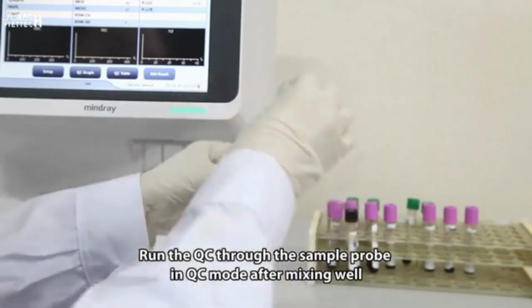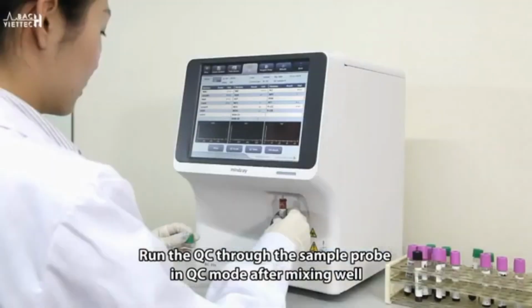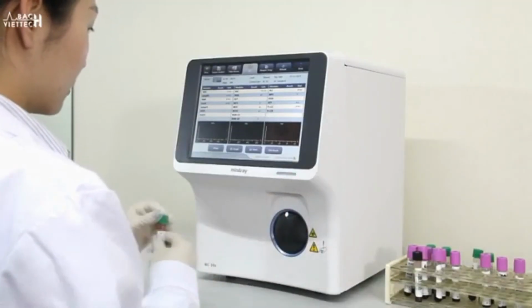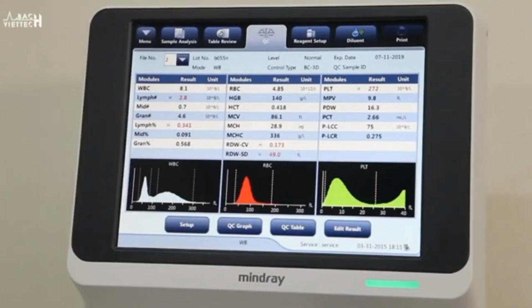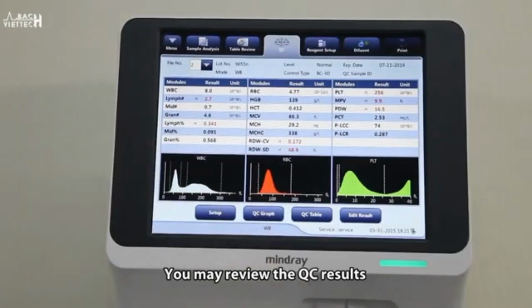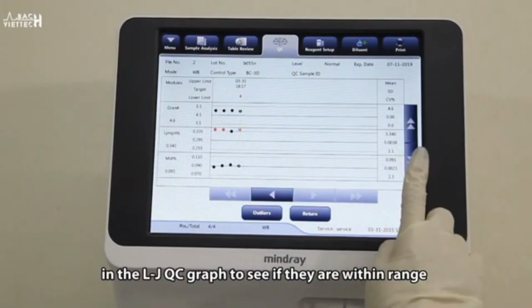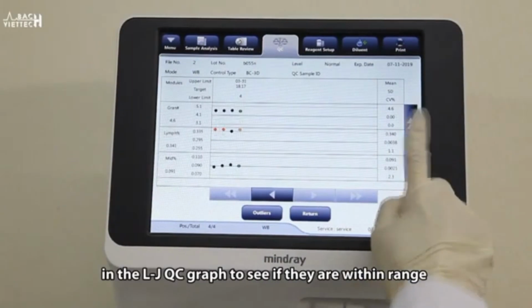Run the QC through the sample probe in QC mode after mixing well. You may review the QC results in the LJ-QC graph to see if they are within range.